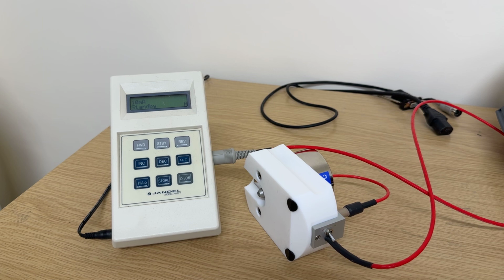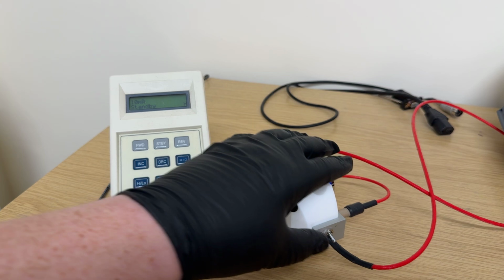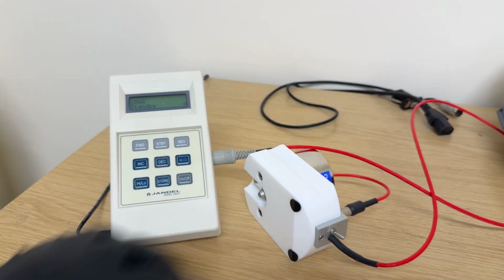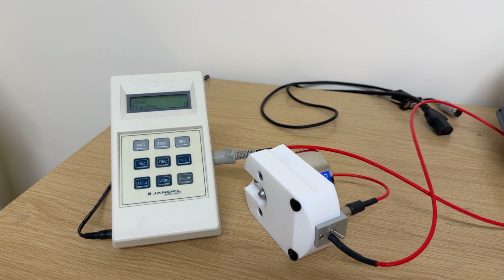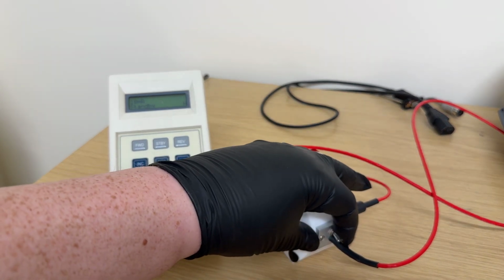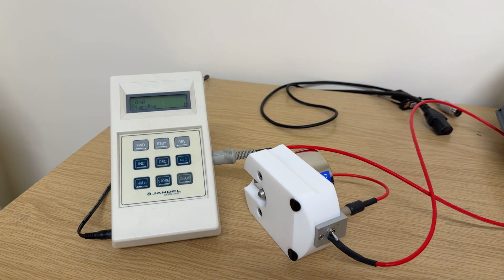This is useful because if you have current flowing when you introduce the probe to a sample, there can be micro arcing. This could substantially reduce the lifetime of your probe head. Once the hand applied probe is in position on a sample, you can flick the switch to R for read to make a measurement. Once the measurements are completed, switch the probe back to S, and you can then remove it and introduce a new sample, or introduce the probe to a different area of the same sample.